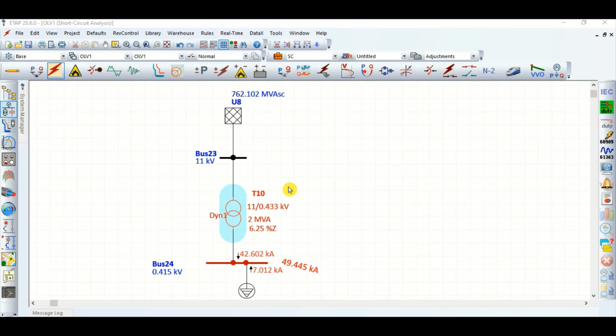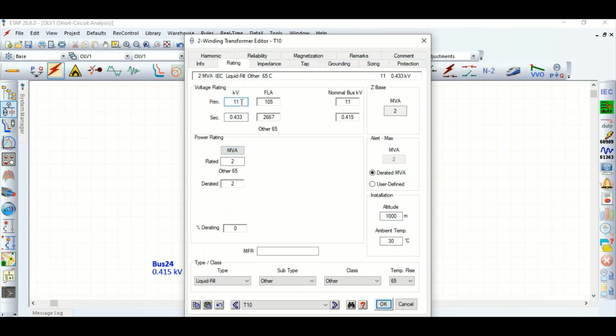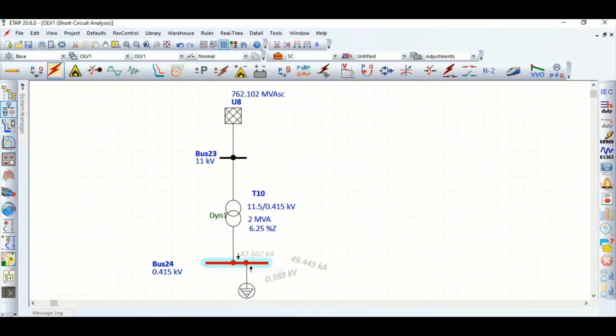Now if we change the primary side rating to 11.5 and the secondary side is 415 volt, the secondary side bus voltage, what will happen? Previously, with 11 by 0.415 kV, it was 53.219. Now let's run this. It is 53.4 kiloampere. That means it is increased. The fault current contribution by the source grid is affected in line with the same explanation I gave for the previous case.